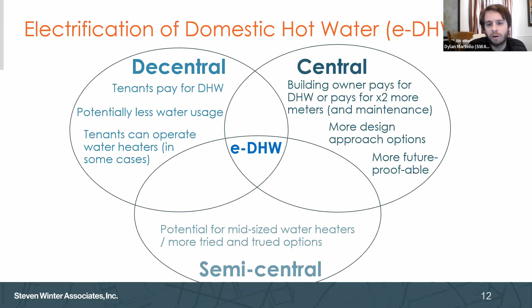Okay, so let's start to summarize some of these options for domestic hot water. When we look at centralized systems, the first option that we'll talk about is air source heat pump water heaters. This is where you have either a large commercial scale rooftop unit on the roof, or you could do a plant style, or you can gang smaller units together to create one air source heat pump plant. That heat pump water heating plant or unit will produce hot water from the outdoor ambient environment. In that scenario, we do need to be cognizant of cold climate performance, and that's where the rubber meets the road with these units: how do they perform in cold climates, particularly the Northeast region, which is what we have experience with.